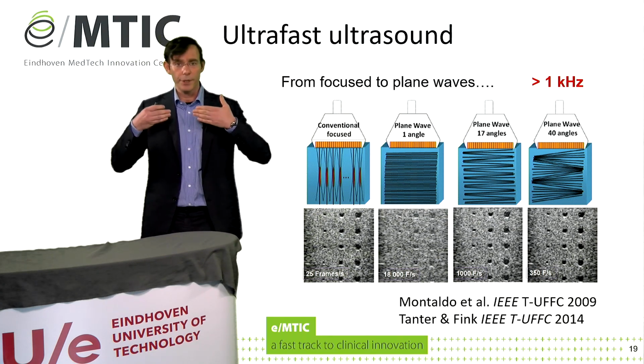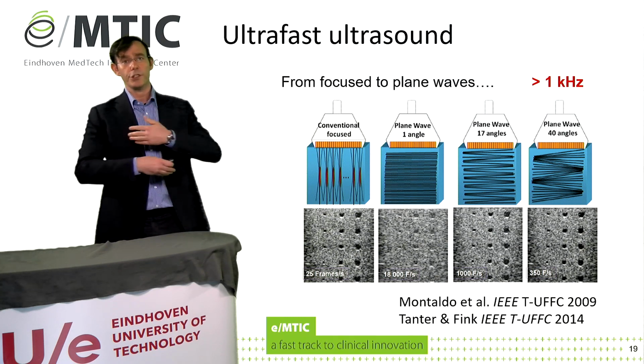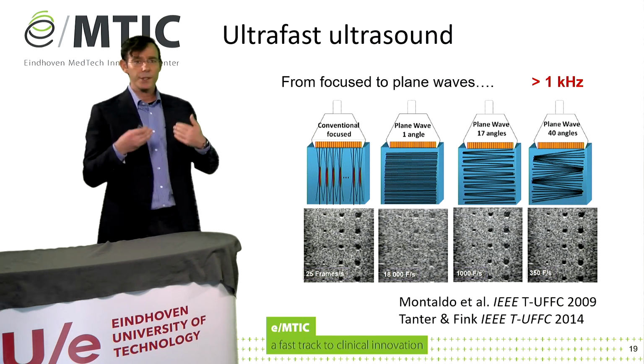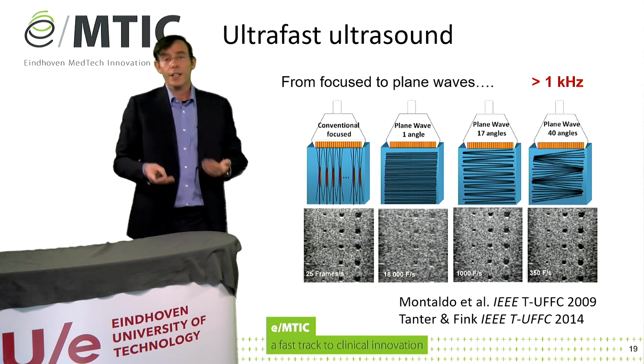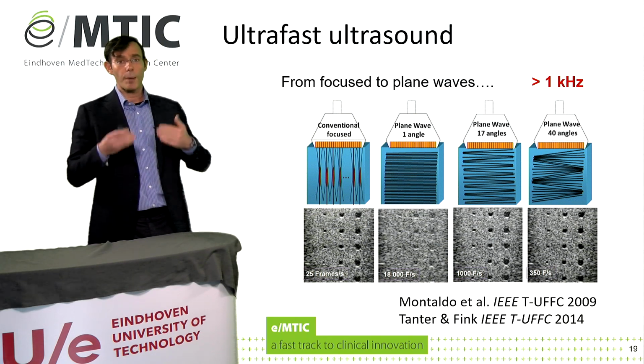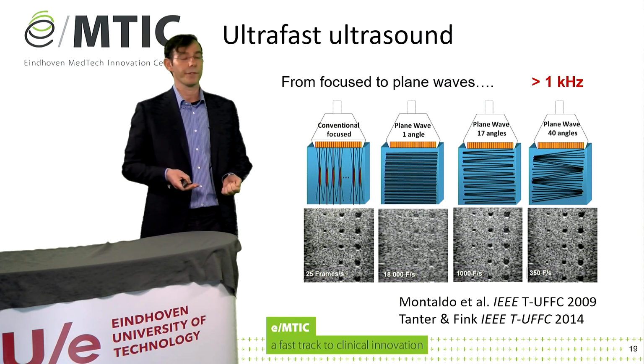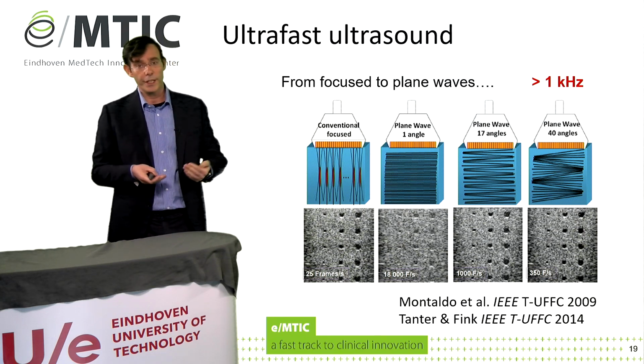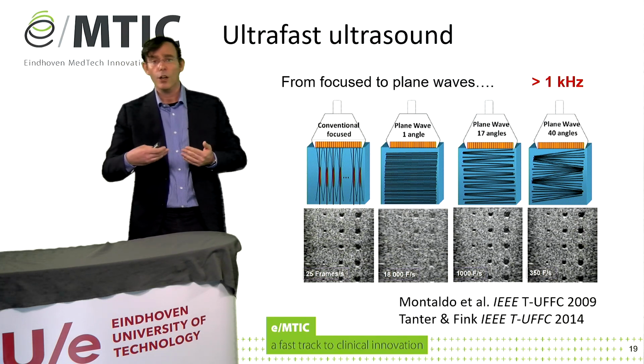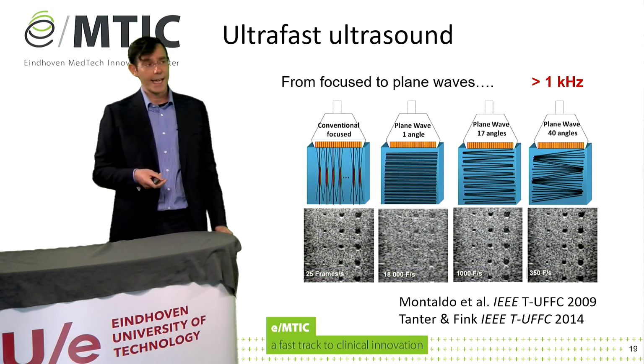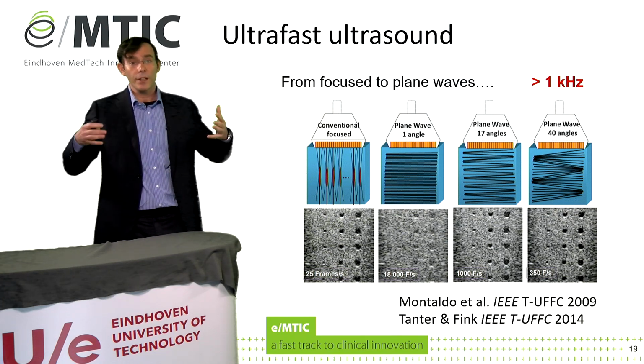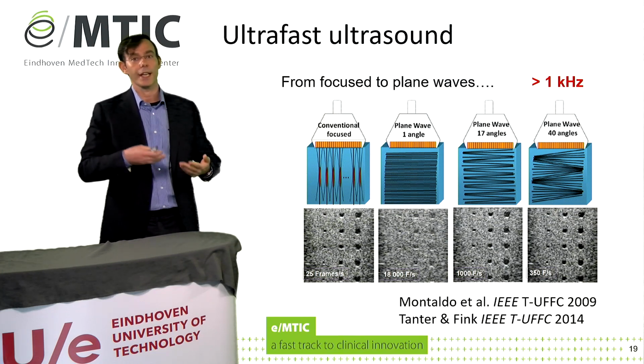So what you do now is transmit a plane wave that will insonify the full field of view, and then you reconstruct the image in receive. So theoretically, with just one plane wave, you can reconstruct the full field of view. Of course, you want to increase the image quality, and therefore you will compound plane waves from different angles. And what you will do is find a compromise between quality and frame rate.